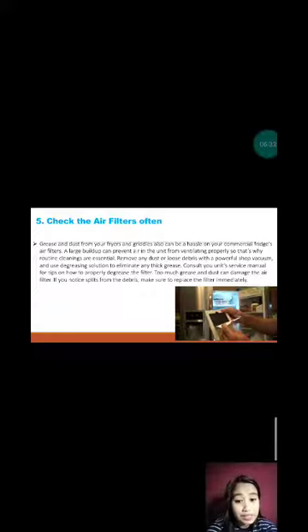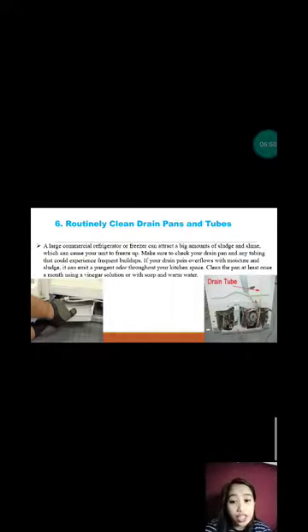So if you notice splits from the debris, make sure to replace the filter immediately, right away. Now, as soon as possible, okay? Alright, so we also need to routinely clean drain pans and tubes, of course, because a large commercial refrigerator or freezer can attract big amounts of sludge and slime. Sludge and slime are the dirt and other unnecessary substances in the drain pans and tubes, which can cause your unit to freeze up.